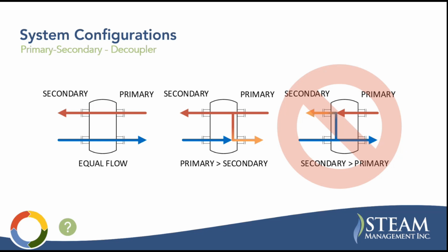Most of the time you're going to have at least some primary flow that exceeds your secondary flow. In that case, you're going to supply some hot water back to your return water, and you're going to get some blending and increase that temperature. And again, that's why this scenario is not ideal for condensing, because you're heating up your return temperature a little bit, and that's not going to promote being in condensing mode.